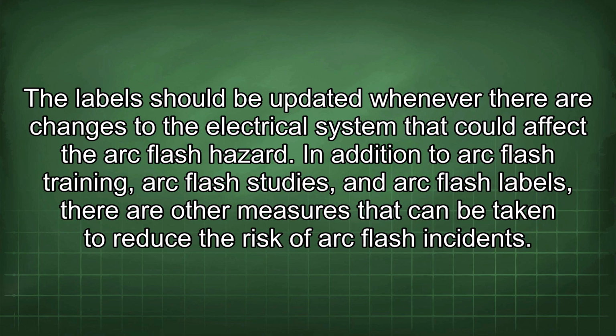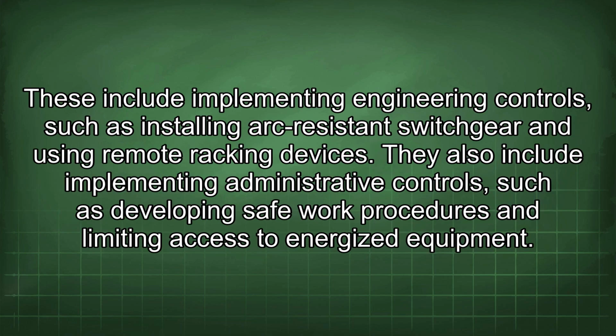In addition to arc flash training, arc flash studies, and arc flash labels, there are other measures that can be taken to reduce the risk of arc flash incidents. These include implementing engineering controls, such as installing arc-resistant switchgear and using remote racking devices. They also include implementing administrative controls, such as developing safe work procedures and limiting access to energized equipment.